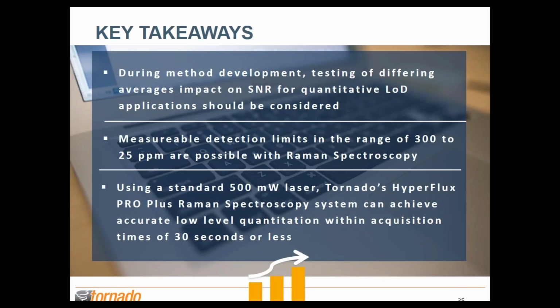The key takeaways. One, during method development and testing, one should consider testing different averages as to their impact on the signal to noise, which in turn affects the capabilities of quantitative LoD applications. So this is not to be overlooked. I make it a standard practice, when evaluating a given chemistry we're looking at applying the technology to, to start with smaller co-adds and evaluate the minimum needed for the desired predictive performance offline. Then I take that information back and use it to set up the instrument for future acquisitions.